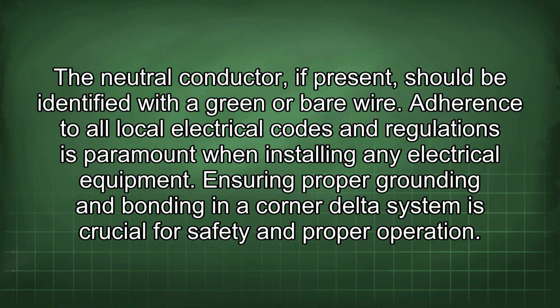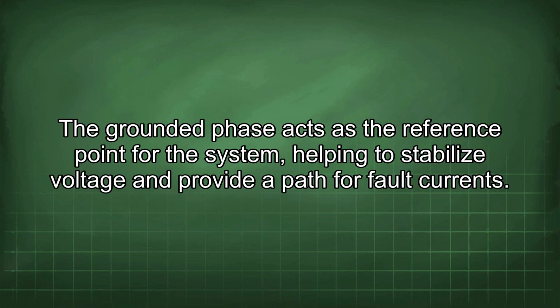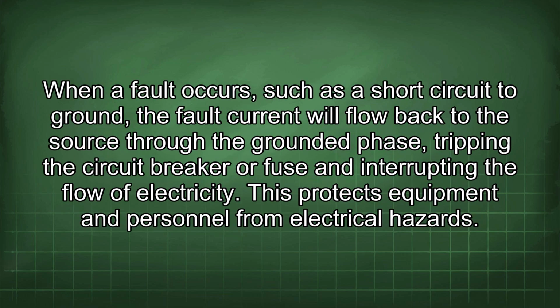Ensuring proper grounding and bonding in a corner delta system is crucial for safety and proper operation. The grounded phase acts as the reference point for the system, helping to stabilize voltage and provide a path for fault currents. When a fault occurs, such as a short circuit to ground, the fault current will flow back to the source through the grounded phase, tripping the circuit breaker or fuse and interrupting the flow of electricity. This protects equipment and personnel from electrical hazards.